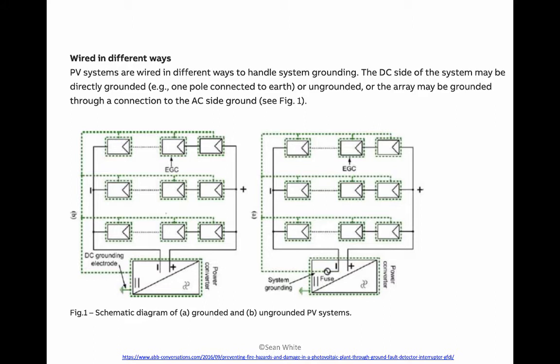So in 2014 and earlier versions of the NEC, we could only use PV wire for these non-isolated inverters. Non-isolated is a word that we can use for the formerly known as ungrounded, formerly known as transformerless inverters. So these inverters that are non-isolated are cheaper, safer, and more efficient than these other inverters that are fuse grounded right here. And as we look around here too, we could see EGC, that stands for equipment grounding conductor, DC grounding electrode right there. That is something that we don't often have to do these days, but we used to have to do.